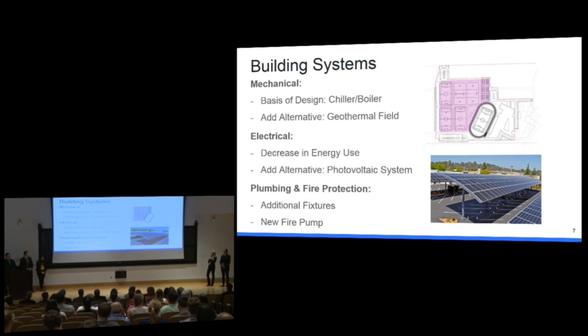All building systems were designed to exceed the minimum codes required by IBC 2012. For mechanical, the basis of design included natural gas boilers and electric chillers connected to water source heat pumps throughout the school, with packaged rooftop units serving individually zoned areas and electric baseboard heaters located in vestibules. Because this is a water-based system, a separate dedicated outdoor air system would be needed in order to meet the ventilation requirements.